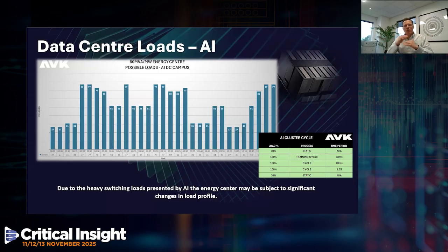It's really important to recognize that if the load changes - and I think we're not 100% sure where the load's going - this doesn't only affect your UPS modules, your lithium ion battery systems, your valve regulated lead acid battery systems. This comes right back to your microgrid or even onto your network. If these AI data centers are doing this to the network, we've got to be very engineering savvy to understand what impact that's going to have.